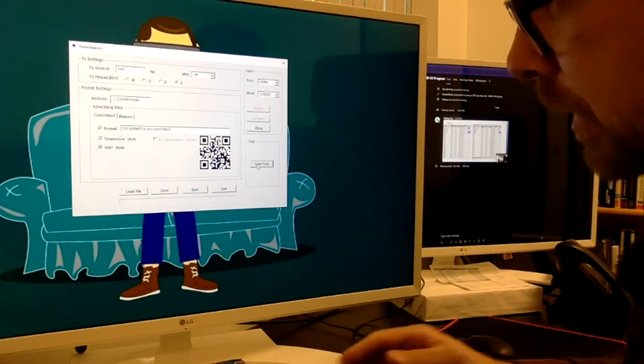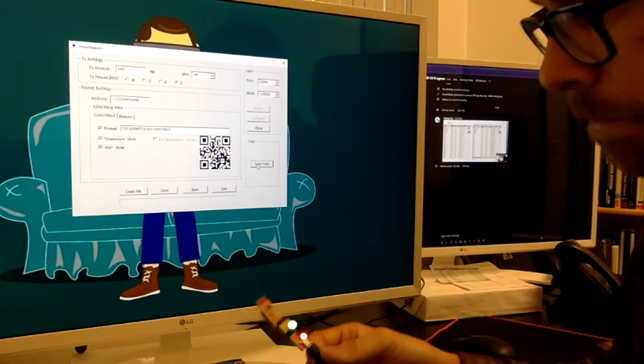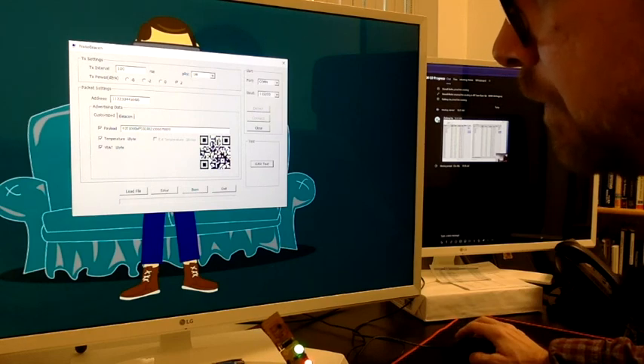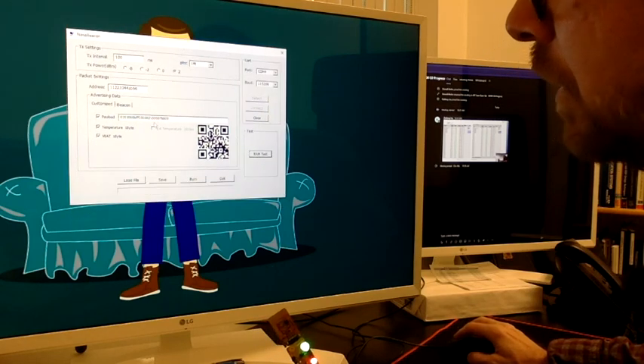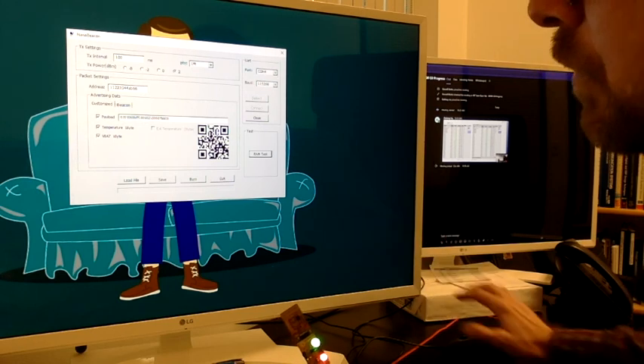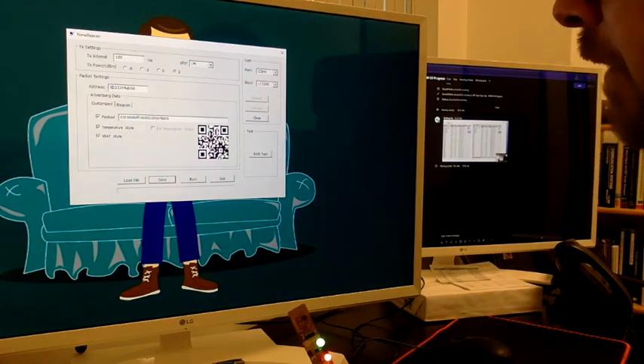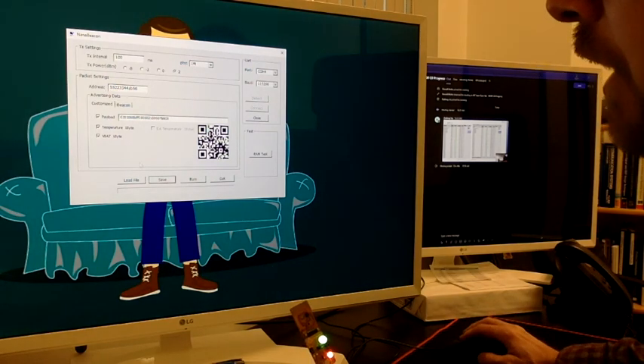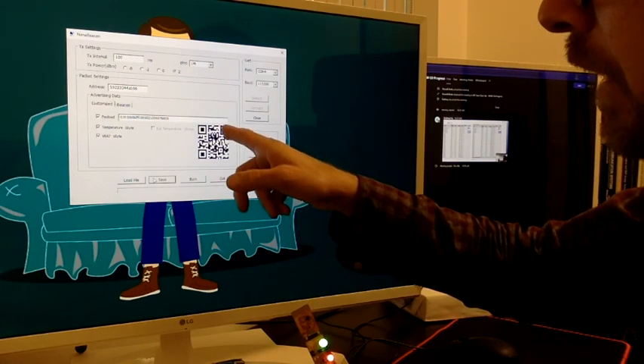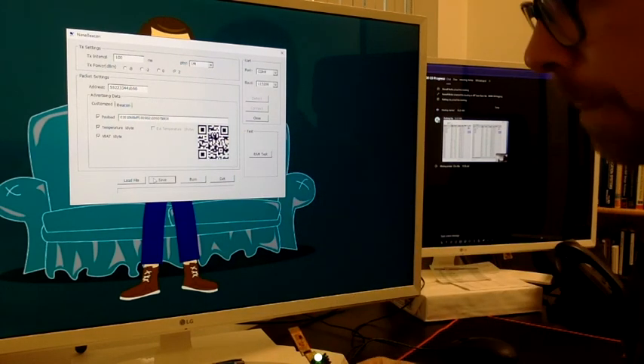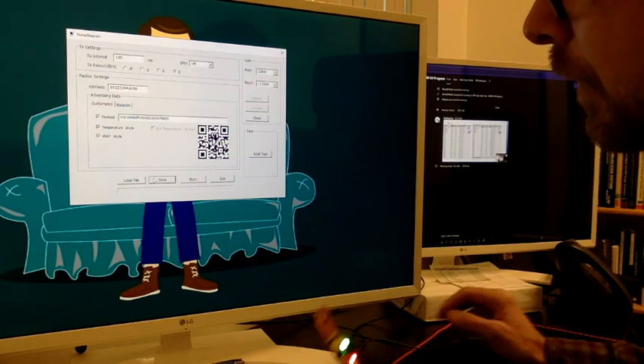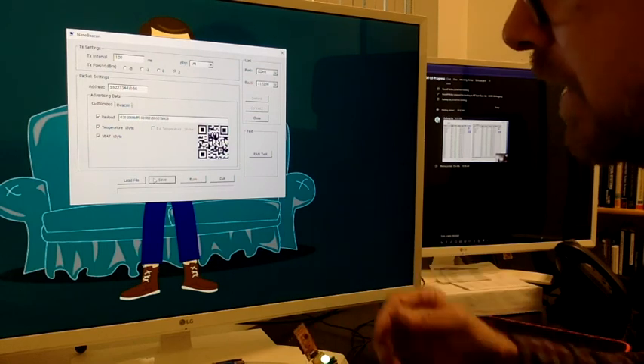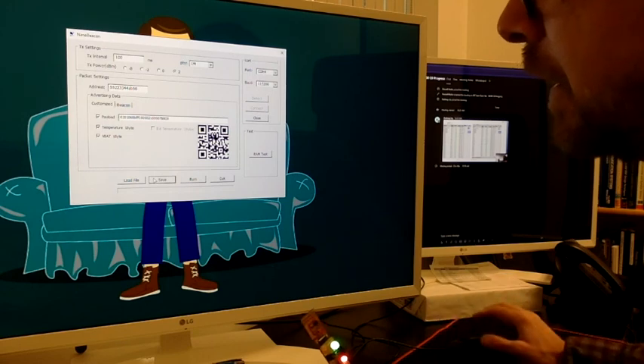So after that's been established, I can actually burn that configuration into the device. Another note on the QR code: if you change the address, for example, let's say we wanted it to be 55 as the address, you have to hit the save button in order to update the QR code and then rescan in order to see that difference in the data.